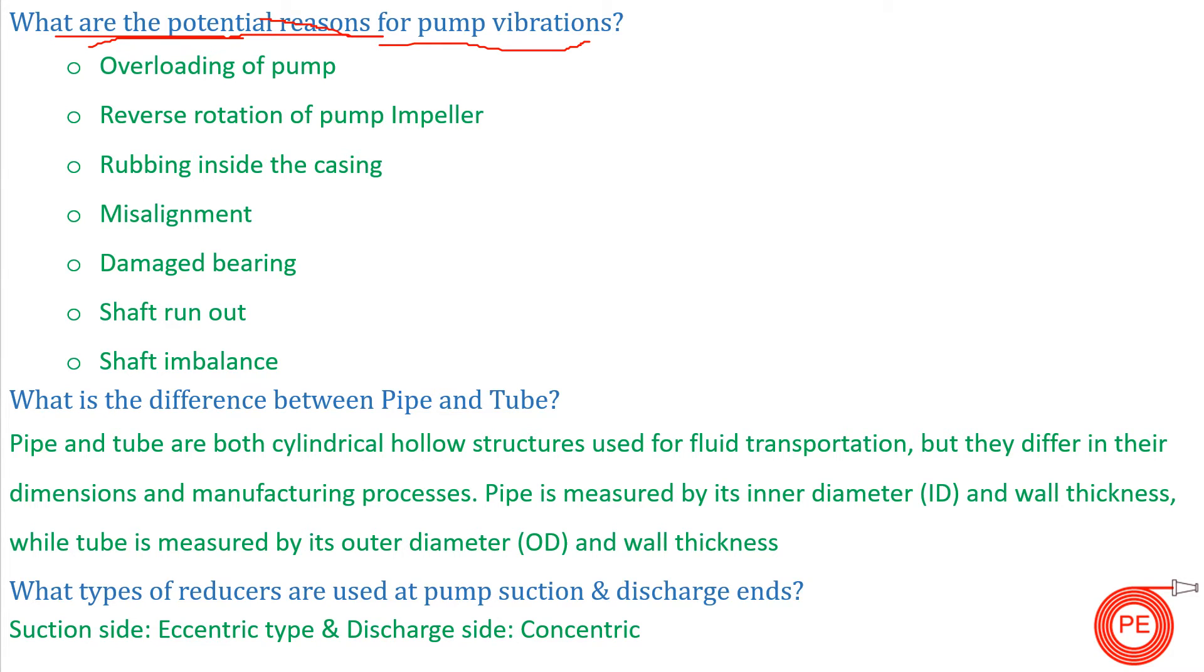Overloading of a pump, reverse rotation of the pump impeller, rubbing inside the casing, if your pump is misaligned, if your shafts are misaligned, if your bearing is damaged, if your shaft is imbalanced—all these things and one of the important reasons is if there is cavitation inside your pump. All these account for pump vibrations, and pump vibrations can lead to pump failure, bearing failures, and a number of problems.